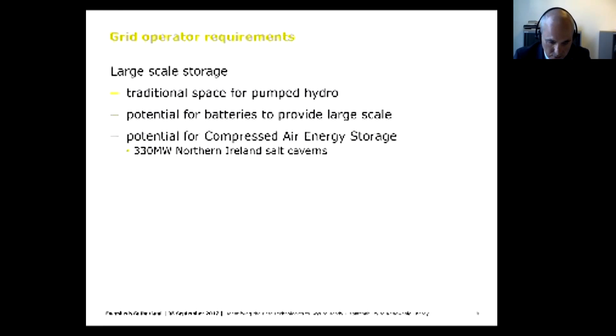So we've looked at the grid operator driving requirements for different storage to compensate for solar and wind. But we also have generators going out to tender for storage, predominantly where they want storage to co-locate with wind or PV facilities. The prime reason for that is to ensure that during peak generation periods they can store energy, for example wind overnight when there's low demand, so they can supply that energy during the daytime. It's also used where there's grid curtailment, not enough capacity on the grid network, or it's too expensive to reinforce the grid network.